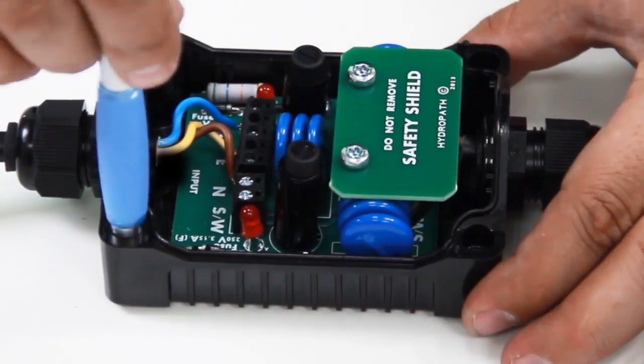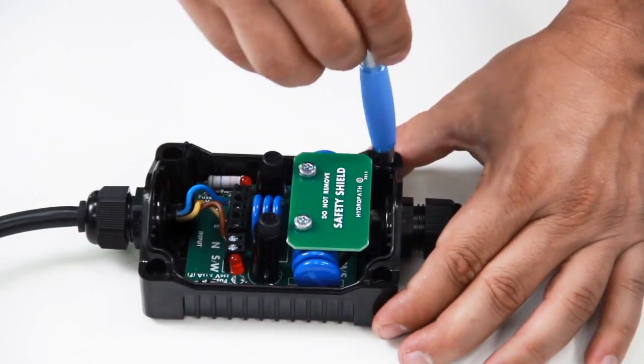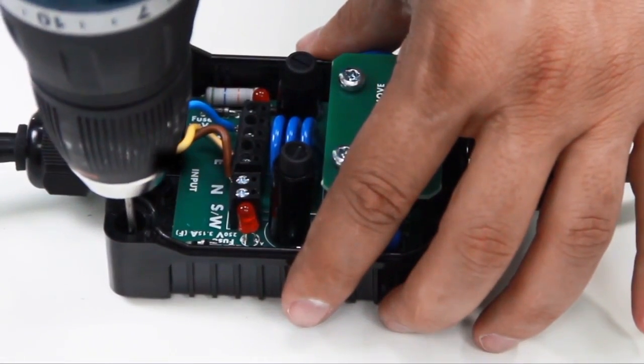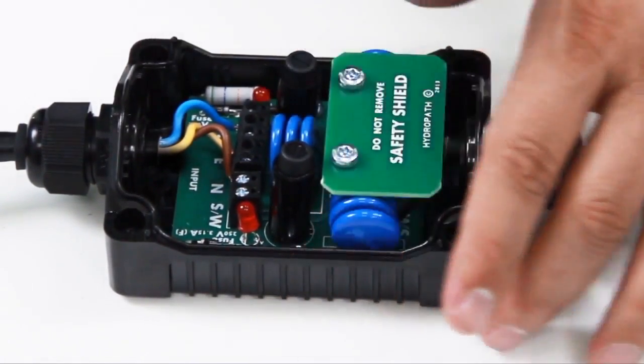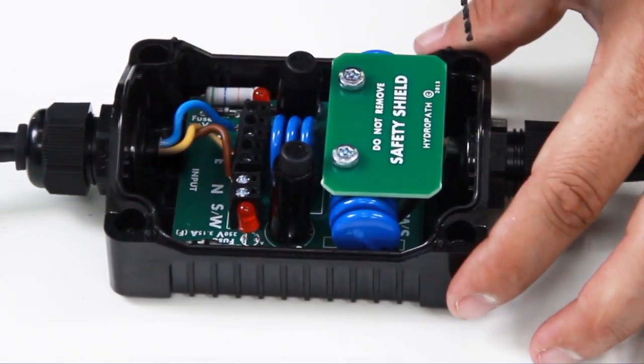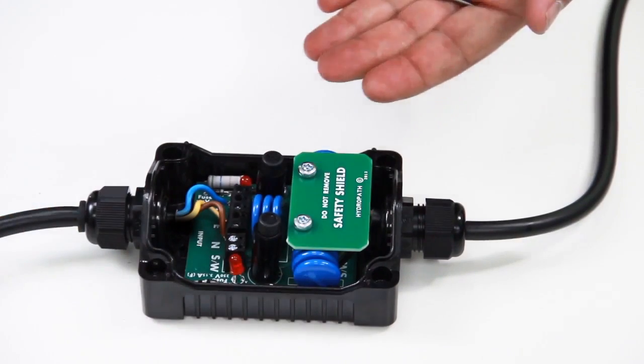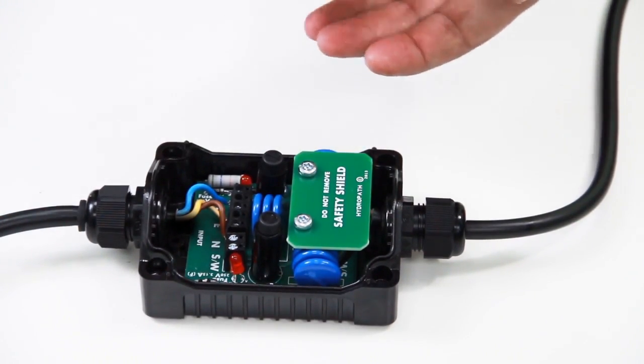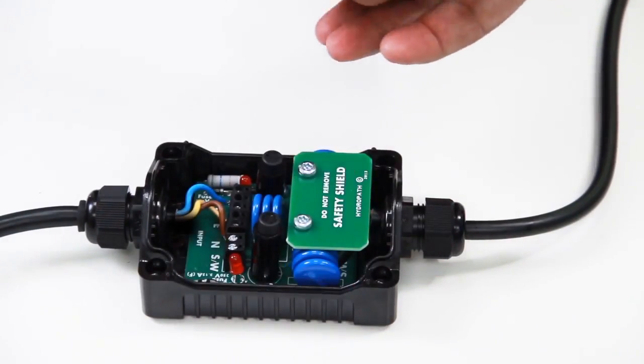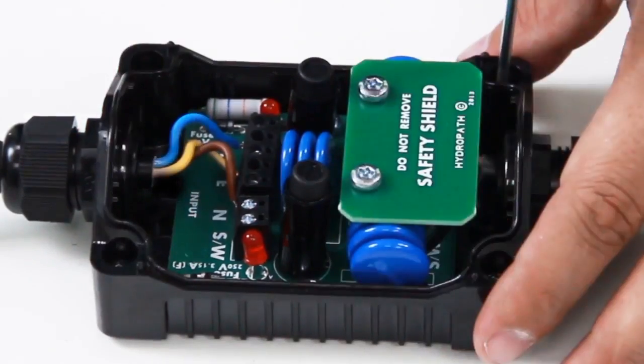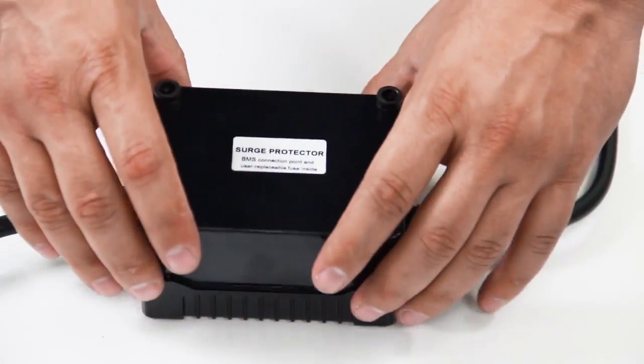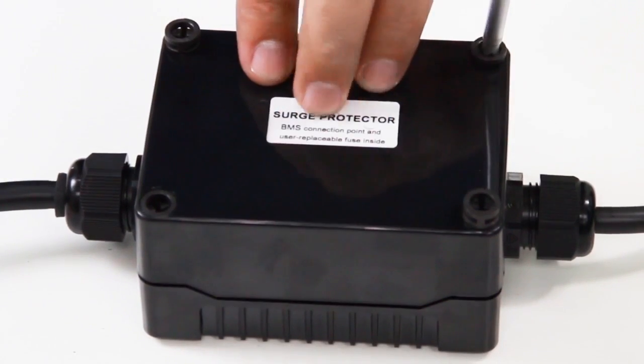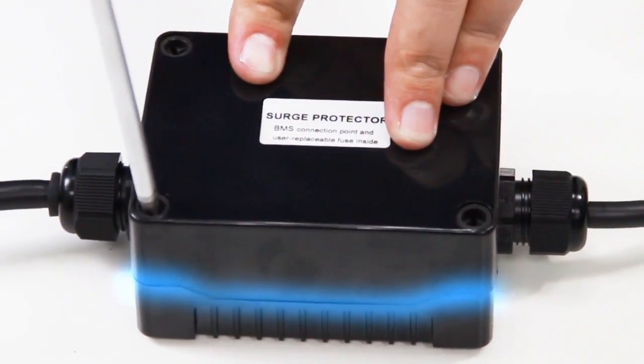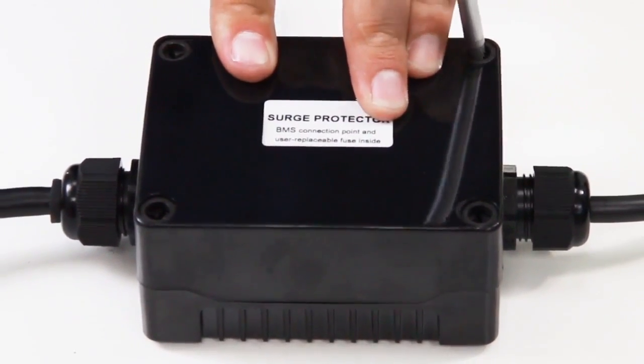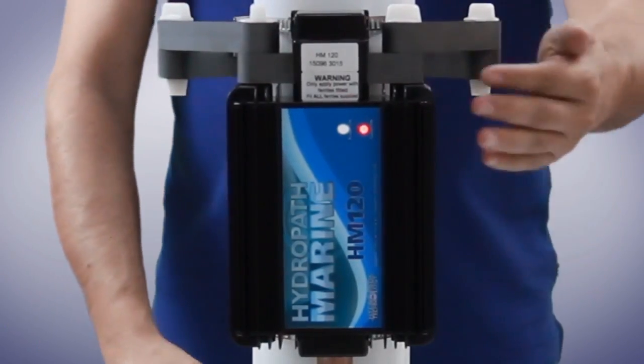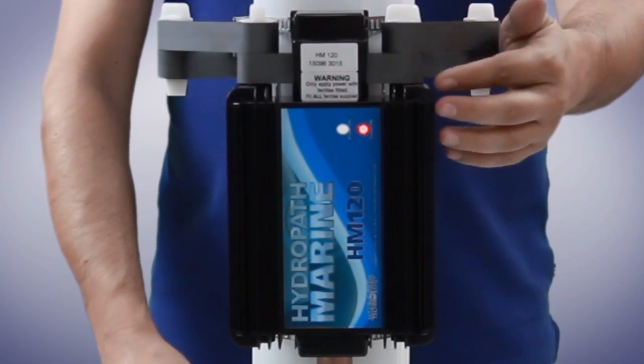Go back to the chosen location of the surge protector and mark for drilling. You can also drill directly through the 4 holes using a 2.2 mm drill bit. Mount the surge protector to its location with the 4 self-tapping screws. Close the cover and screw it back diagonally. Make sure there is no gap between the surge protector box and its cover. Finally, connect the cable to a permanent power supply. You're all set!